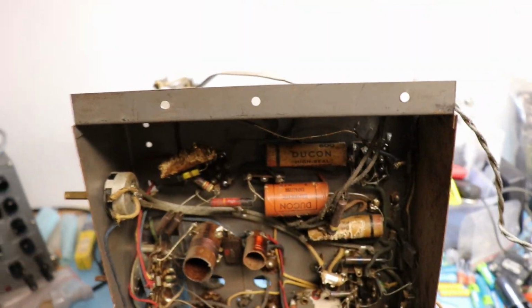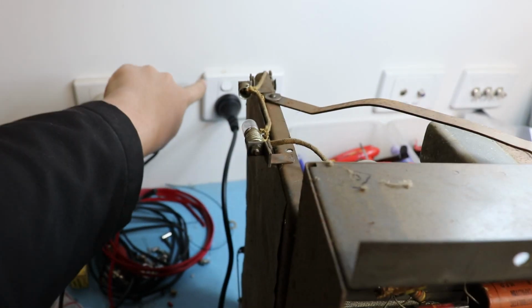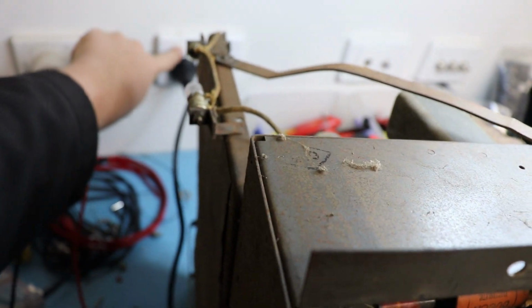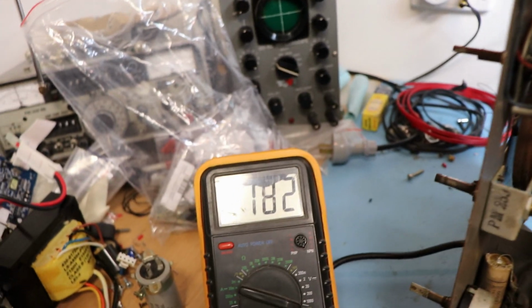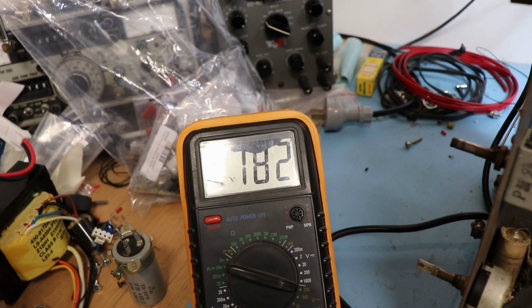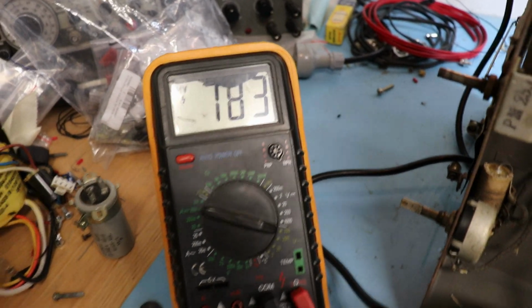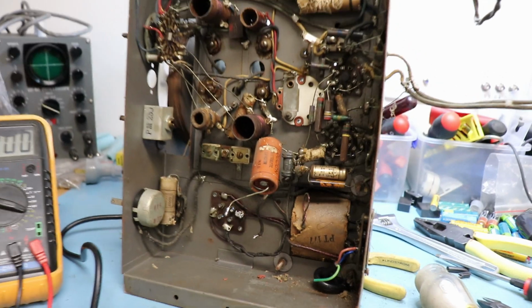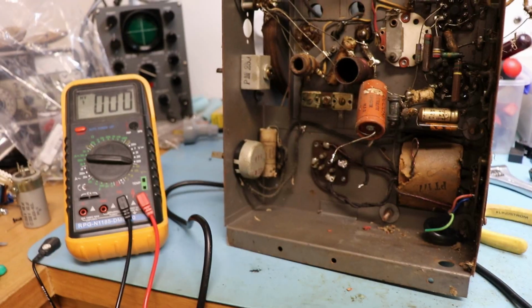So I've got the meter set on AC, so if it works, the light will go on, which it has. So there's high voltage across these 2 terminals, 782 volts AC. So turn that back off. That transformer is working, no problems.